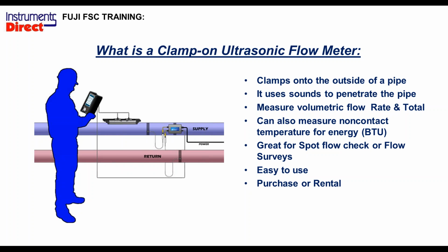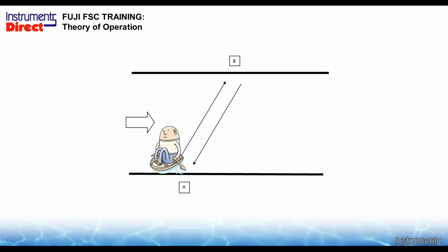It's ideal for spot checks of flow. So we just put it on the pipe and say, here's the flow right now, or you can leave it there for an extended period of time. It comes in different shapes and forms, portable and dedicated. Today we're going to focus on the Fuji Portaflow-C series. We have made it very easy to use. Little to no training. Operation manuals, we have quick starts that are 1 or 2 pages long. And for access to the equipment, you can buy it or you can rent it. So those are some of the values of a clamp-on ultrasonic flow meter.